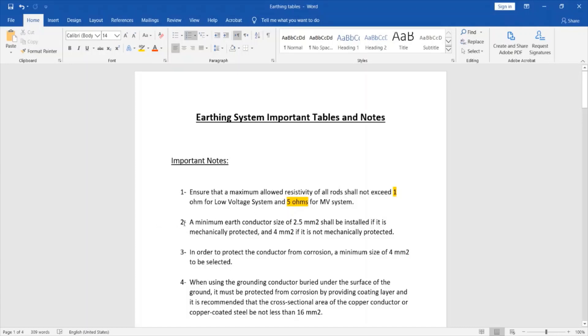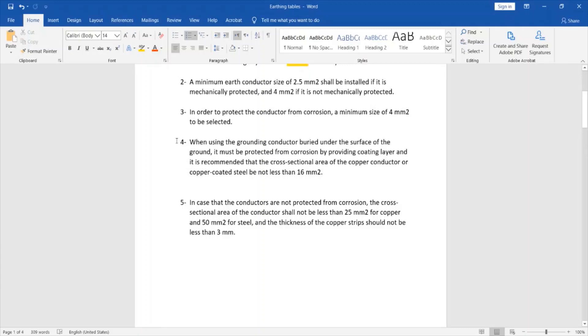The second note states that a minimum earth conductor size of 2.5 millimeters squared should be installed if it is mechanically protected, and 4 millimeters squared if it is not mechanically protected. To protect the conductor from corrosion, a minimum size of 4 millimeters squared is to be selected. When using a grounding conductor buried underground, it must be protected from corrosion with a coating layer, and it is recommended the copper conductor cross-sectional area be not less than 16 millimeters squared. If conductors are not protected from corrosion, the cross-sectional area shall not be less than 25 millimeters squared for copper or 50 millimeters squared for steel, and the thickness of copper strips should not be less than 3 millimeters.